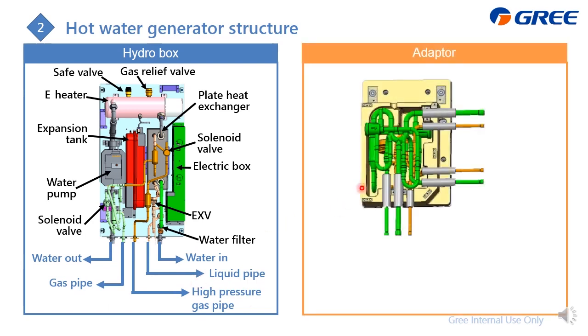For the adapter, open the panels. Here is the inside. You can find that here just connect with the 3 pipes to the outdoor unit. This is to the indoor unit and the water tank. And also inside there are 1 EXV and 2 solenoid valves to control the refrigerant.